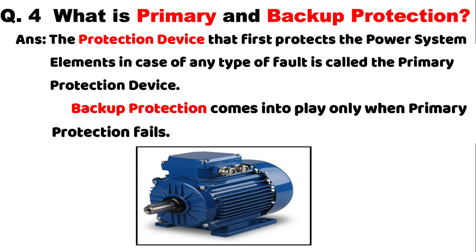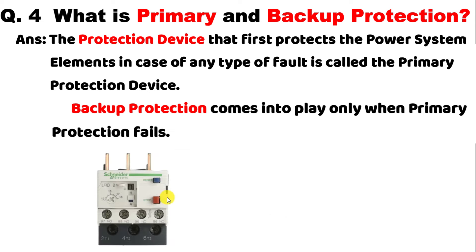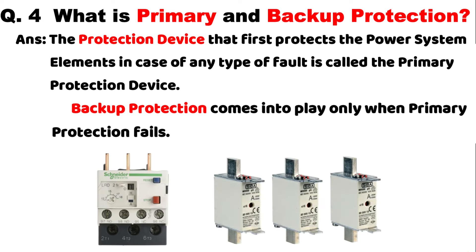To understand this clearly: for a motor, we use a starter connected with the motor. In this starter, an overload relay is used for protection of the motor — this is the primary protection. Also in the starter there is a fuse, which is the backup protection. If by chance the overload relay does not work, then the fuse will provide the protection.